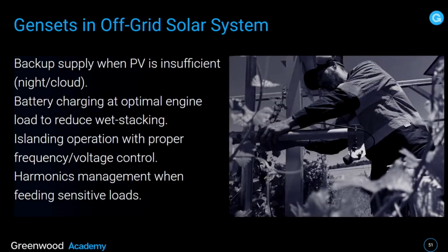Gensets in off-grid solar systems. In this situation, we're looking at backup supply when PV is insufficient, night or cloud. Battery charging and optimum engine load to reduce wet stacking. Islanded operation with proper frequency and voltage controls. Harmonic management when feeding sensitive loads. So there are a few factors to think about.